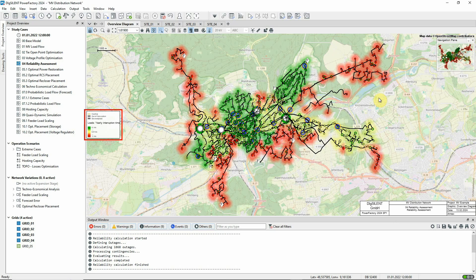It's colored to indicate the yearly interruption time, which is calculated for loads. The areas colored red are likely to experience over one hour per year of interruption to supply, and it can be seen how the extremities of the network are weakest in this respect.